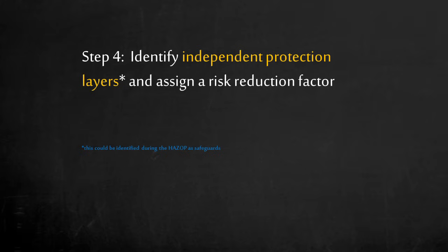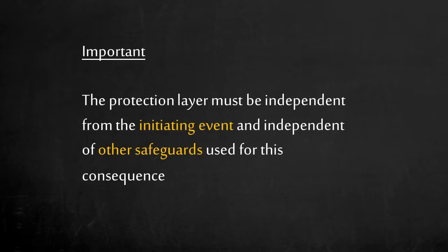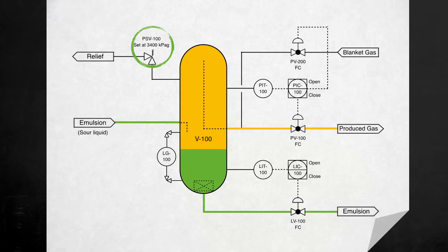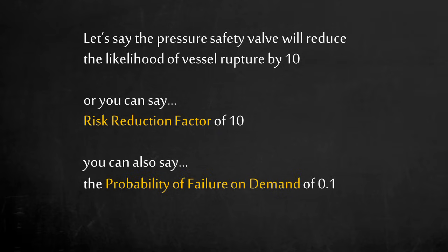Step 4: identify the independent protection layers in the system. These are mechanisms which prevent the consequences from occurring, and are the safeguards identified during a HAZOP. To assign a safeguard as an independent protection layer, it must meet specific requirements defined by international and regional standards. The protection layer must be independent from the initiating event and other safeguards. There is a pressure safety valve on the vessel — PSV100 will protect V100 from overpressuring. This valve can reduce the likelihood of vessel rupture by a factor of 10, expressed as a risk reduction factor of 10 or a probability of failure on demand of 0.1.